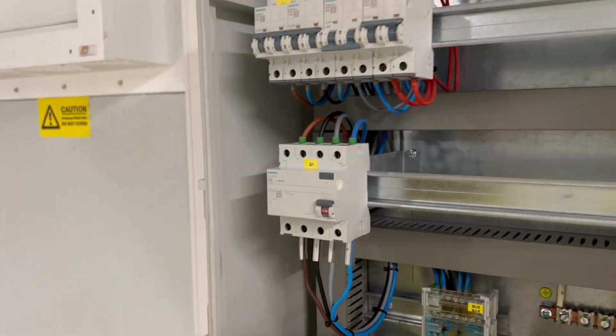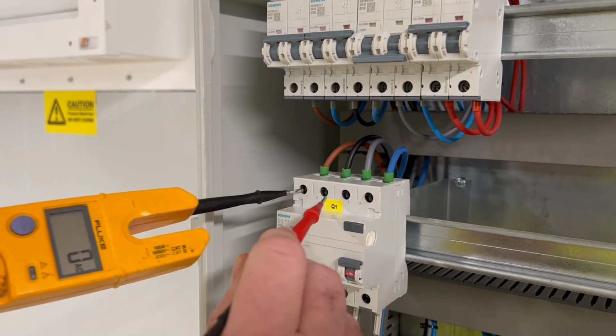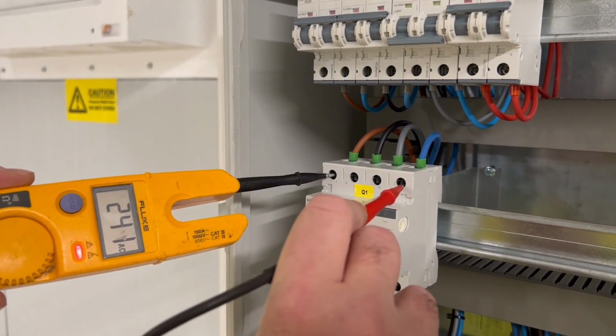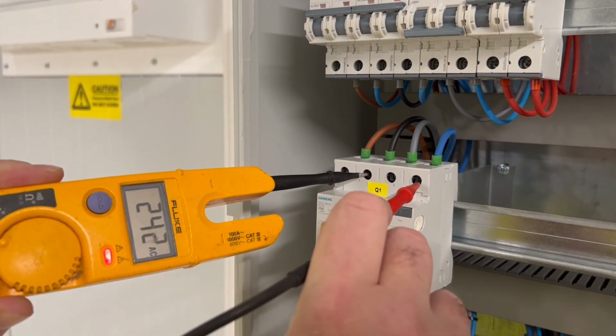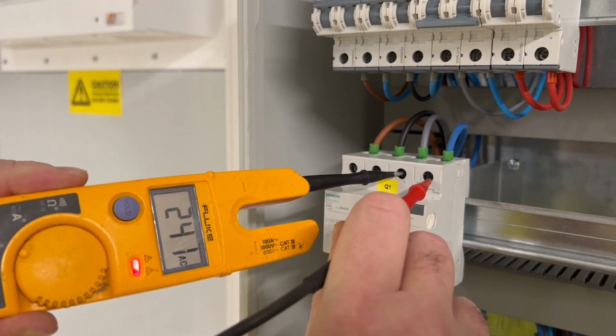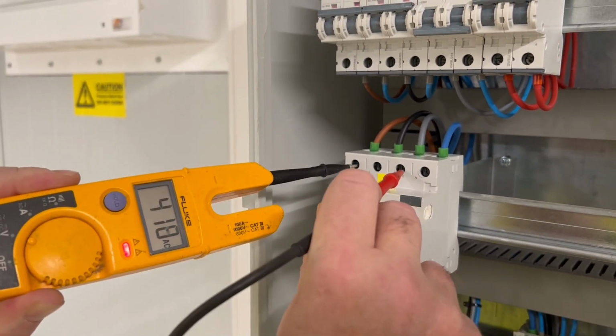First test is just to check the internal resistor trip, make sure the internal function works, and then we're going to check each phase in turn to make sure everything is balanced and we're happy with the voltages we've got on the system at the moment.